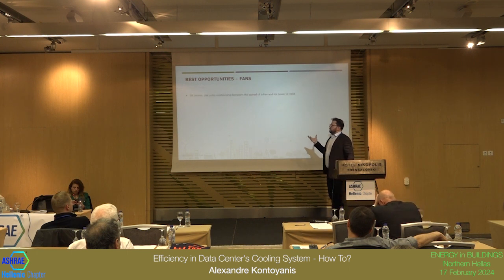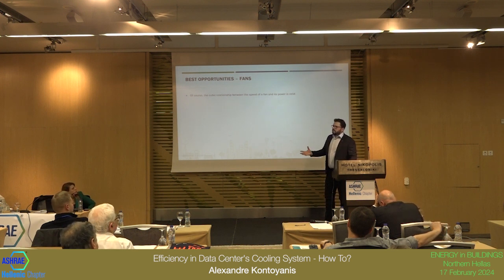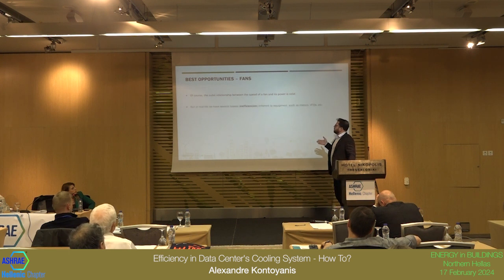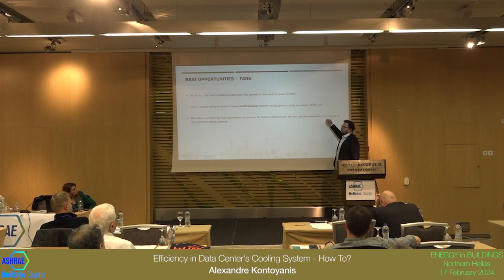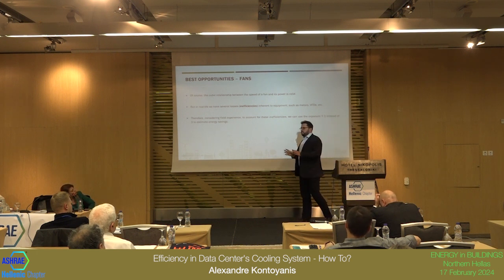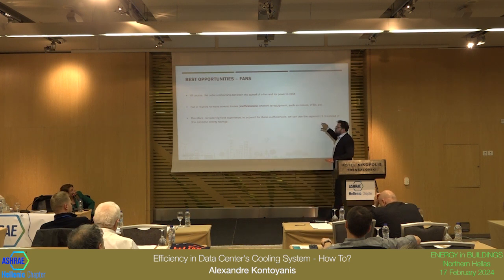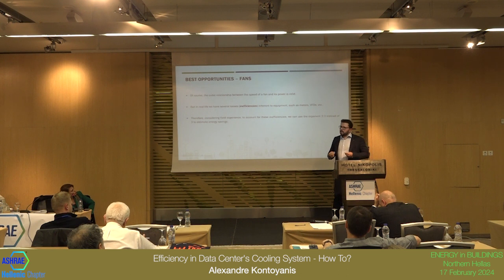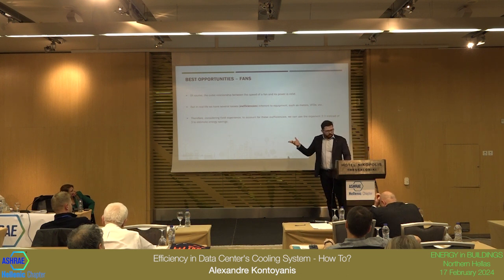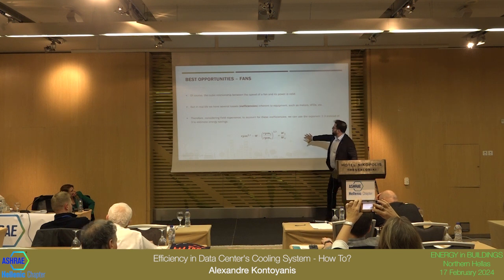The important thing to say is this is a physical law. It's not from the parliament. It just happened. God wanted it like this. But in reality, connected to the fan, we have motors, belts, VFDs. We bring some inefficiency with these. And from the field, we found that if you change the exponent 3 to 2.3, it gets as close as can be to reality. So if you change the exponent from 3 to 2.3, you will have a good idea how much energy you can save. You can use the equation like this.